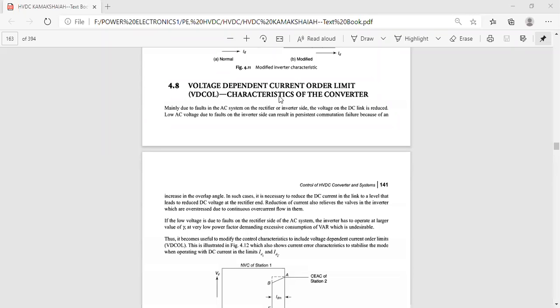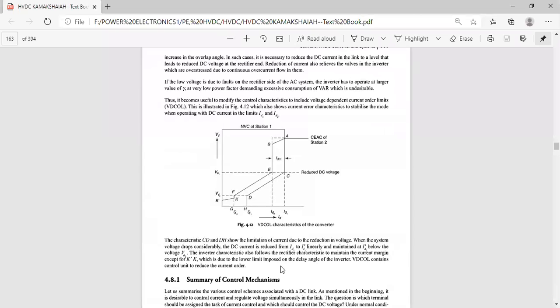Let us discuss the voltage dependent current order limit (VDCOL) characteristics of the converter. On the y-axis we are taking Vd and on the x-axis we are taking current. In the Vd-Id characteristics, Vd is the direct voltage of the DC transmission line and Id is the direct current. This is the characteristic of the rectifier and this is the characteristic of the inverter.